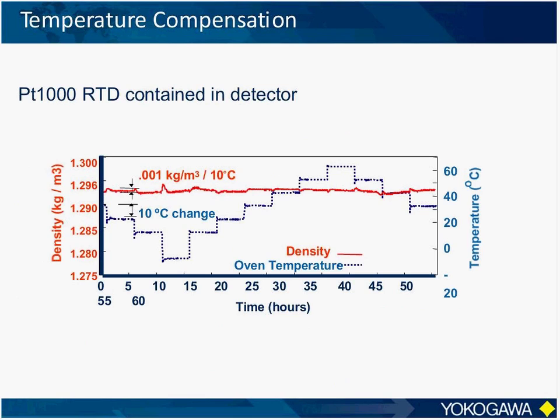What the illustration shows here is a test where a vibrating element detector is placed in a climate-controlled chamber and is exposed to temperatures that are ramped up and down, and you can see that there's very little effect on the density measurement itself.